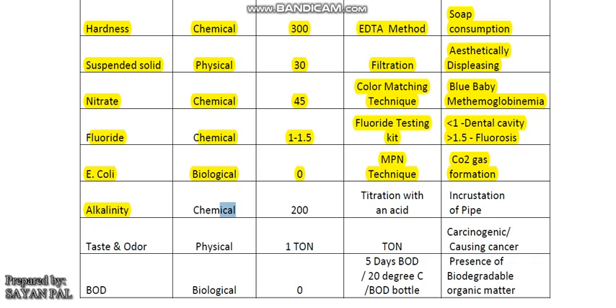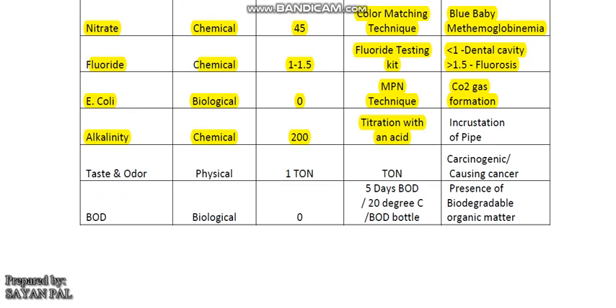Then, alkalinity is a chemical water quality parameter. Alkalinity means the ability of water to neutralize H⁺ ions. It is measured by titration with an acid, generally 0.02 normal H₂SO₄. Its acceptable limit is 200 mg per litre and its cause-for-rejection limit is 600 mg per litre. It causes incrustation of pipe: CO₃²⁻ reacting with Ca²⁺ causes CaCO₃, and its precipitate in the pipe causes incrustation.